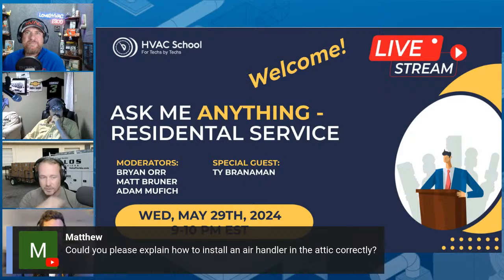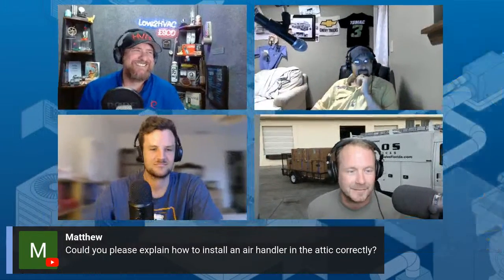And make sure your ductwork is well attached. So especially if you're doing a board and mastic situation, don't just let the mastic be the thing that supports those ducts. They have to be independently and solidly supported right at the equipment. I've seen a lot of ducts fall off - I'm talking about ducts specifically.